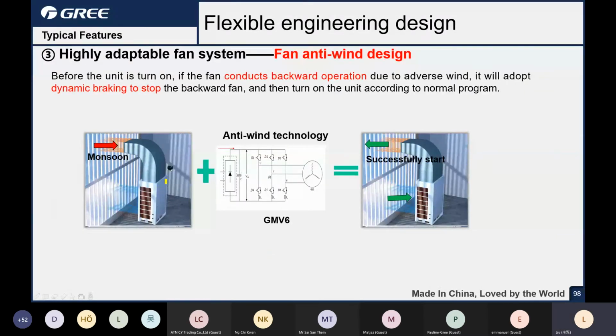And this is the fan anti-wind design, especially when you install the discharge ducts to other units. If there is monsoon or heavy wind, it may cause the fan motor of other units to run reversely. And for the GMV6, there is a circuit that connects with the fan motor to detect the rotation direction and the speed. So if the running direction of the fan motor is reversed, the unit will stop the fan motor immediately and drive the fan motor to run normally. There is a circuit detection for the fan motor running direction.